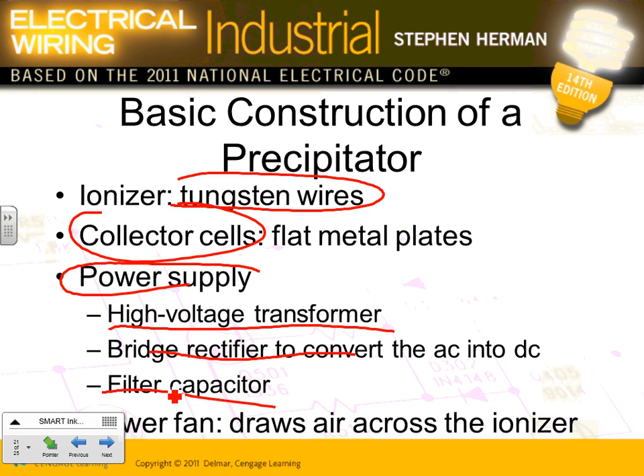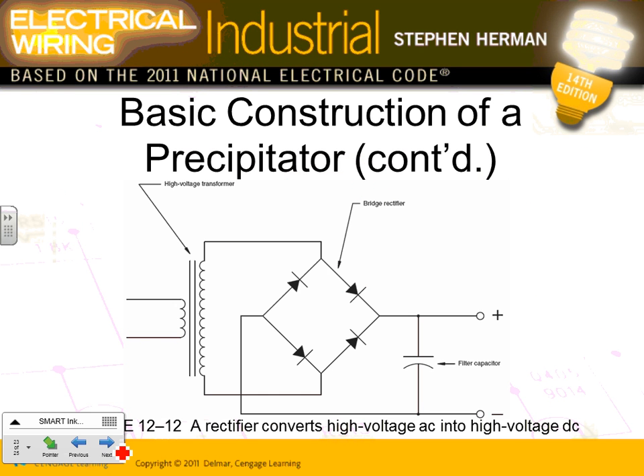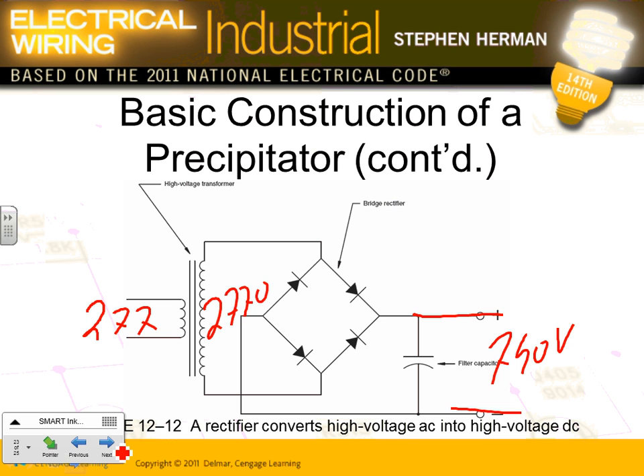It has a high voltage transformer and a rectifier. So Jeff, how does it do? Look at this. It takes your voltage right here. Let's just say 277 volt. It pumps it up to a high voltage, I know, 2770. It rectifies it to a higher voltage. I'm just going to throw a voltage here, like 750 volt DC. I might be off the wall here. Now we got DC, you put it across that mesh, and you throw the air through it, ionize the particles in the air, and as it ionizes, it sticks to the negatively charged filters. Now you clean your air.